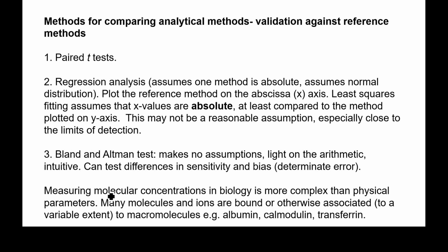But there's a test called the Bland-Altman test, which is widely used in the field where it was developed, which is clinical sciences. But it's a really great way of comparing analytical methods, and I'm encouraging people to use this more widely when you're comparing one measurement technique with another. It makes no assumptions as to which method is correct. It's light on arithmetic, and I think it's also intuitive for most people to understand. And it allows you to test for differences in sensitivity and bias, i.e. determinate error. So what you do is you plot differences versus means.